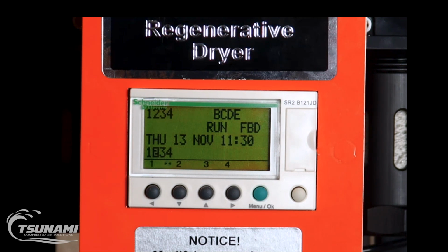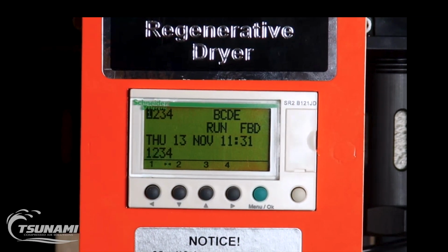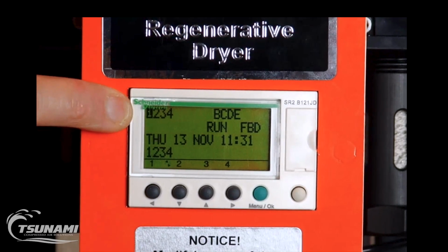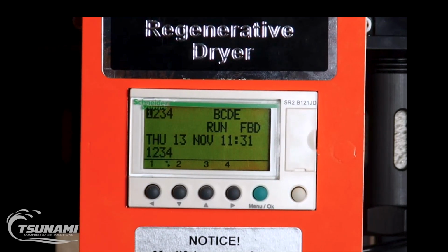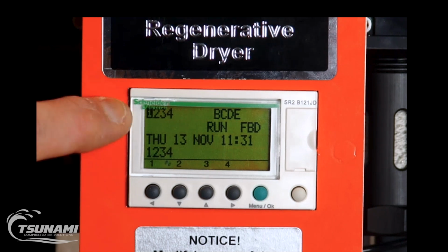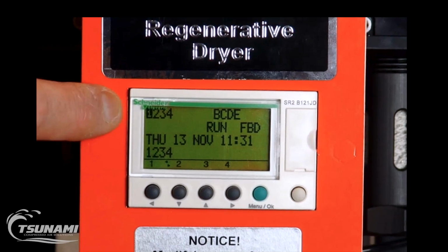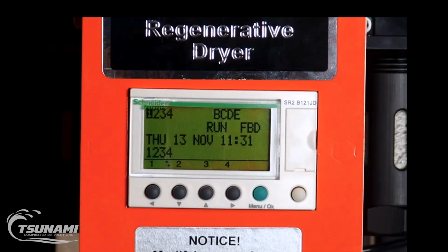Whether it's dry contacts or pressure transducers, these signals all work on the same feature. So when we start talking about parameters 4 and 5, that's really why understanding how some of those controls work is important. Let's assume that this dry contact or this pressure transducer turns on when the compressor is loaded. If that's the case, we want this dryer to be running when that input is turned on. Right now it's not running because parameter 4 and 5 are set at zeros.